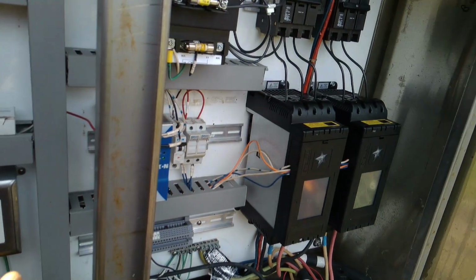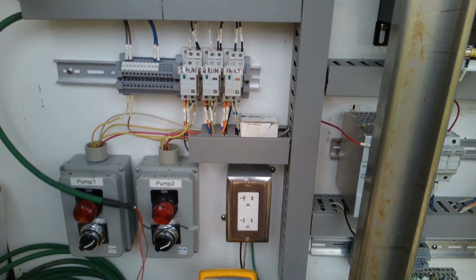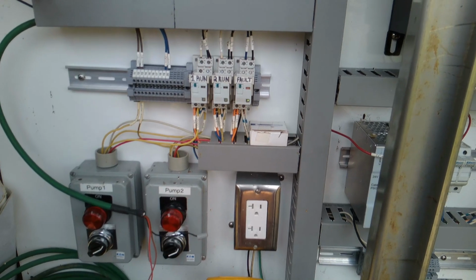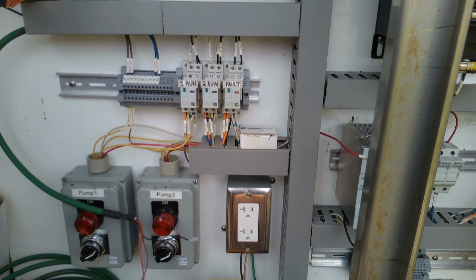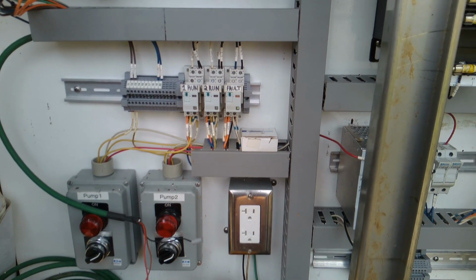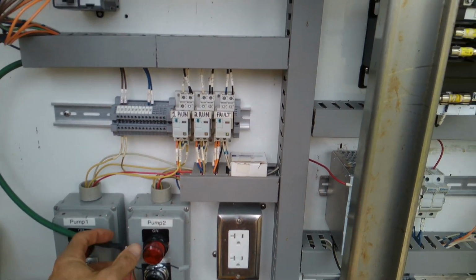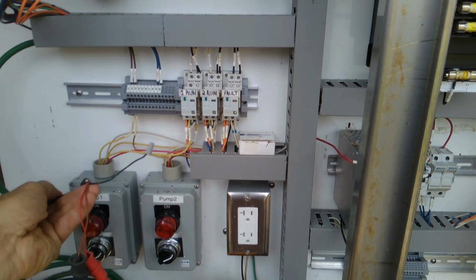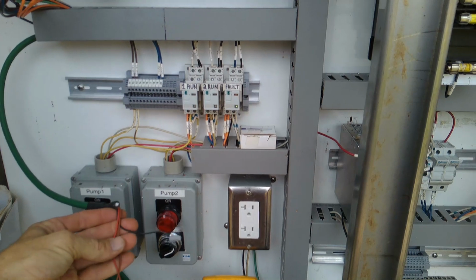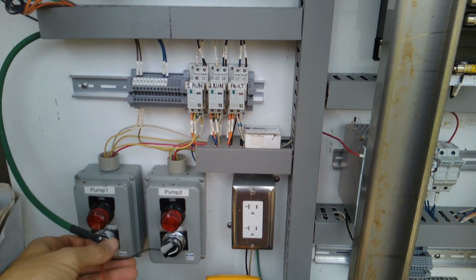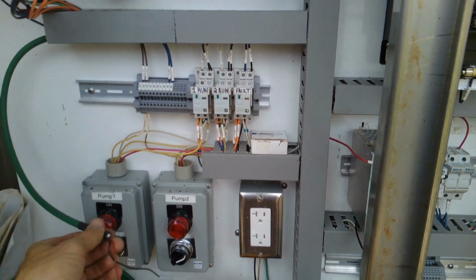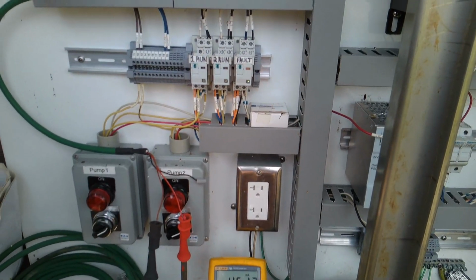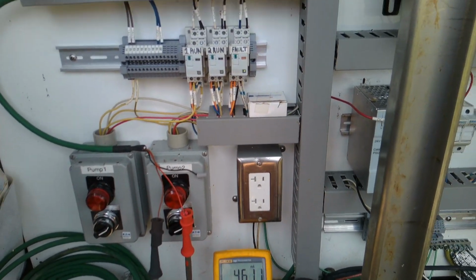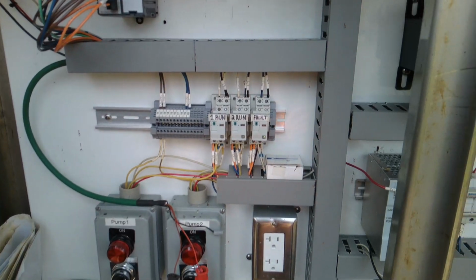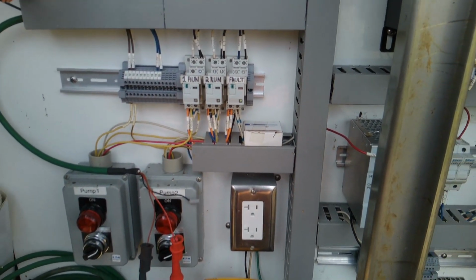It isn't flickering anymore, though. I will say that. That's a good sign. And I'm not seeing too much of a jump. It really usually doesn't move at all, but it's only jumping 1 or 2%. I know we have a really tight bandwidth here though, between start and stop. So, okay, let's connect to the PLC with the transducer connected and see what kind of signal we're getting. Turn this off.